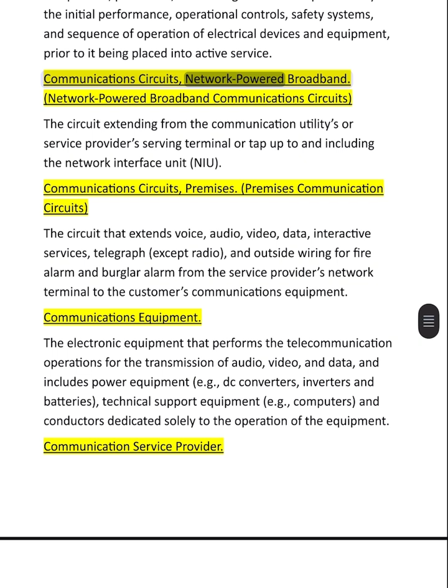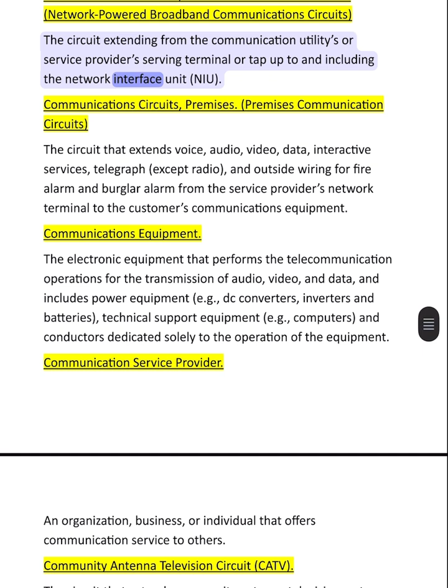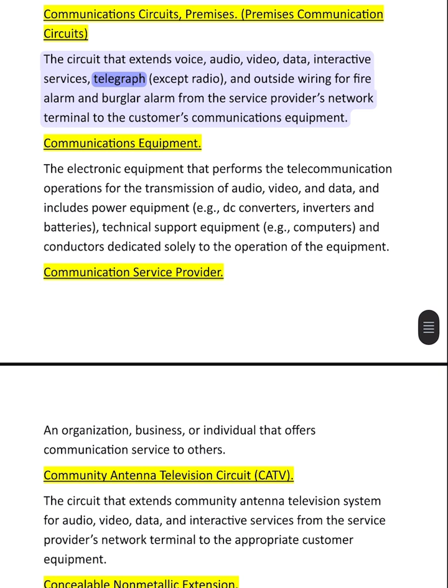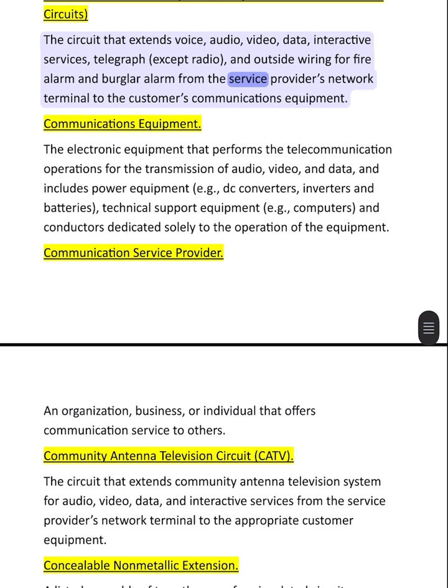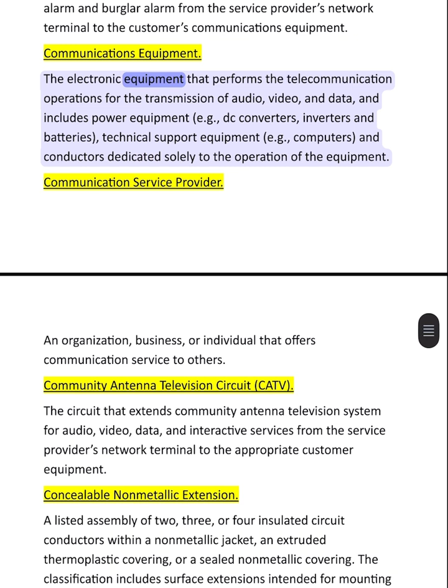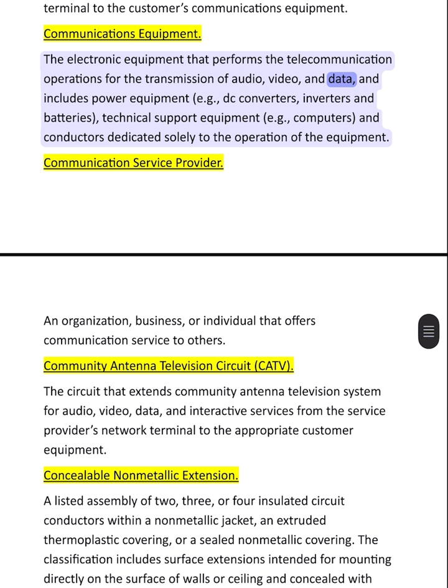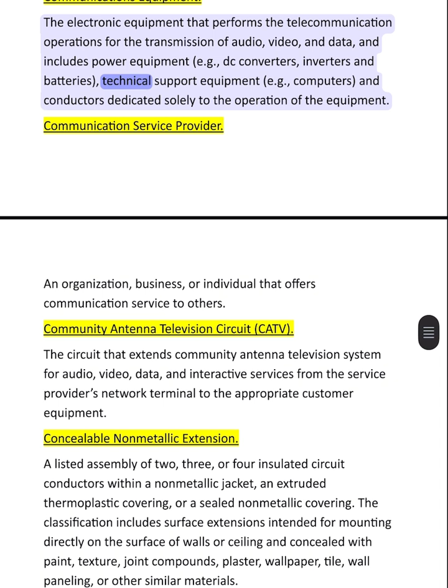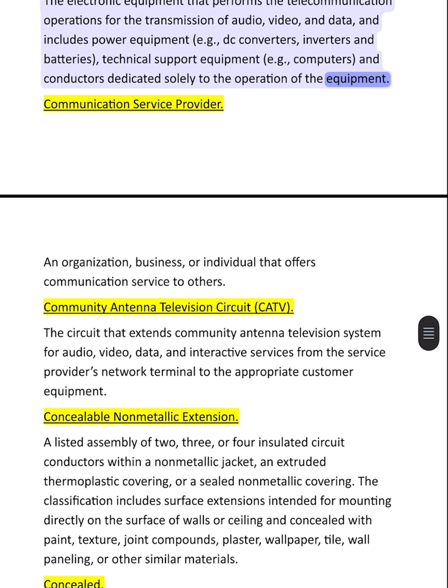Communication circuits, network-powered broadband. Network-powered broadband communication circuits. The circuit extending from the communication utilities or service provider's serving terminal or tap up to and including the network interface unit, NIU. Communication circuits, premises. Premises communication circuits. The circuit that extends voice, audio, video, data, interactive services, telegraph (except radio), and outside wiring for fire alarm and burglar alarm from the service provider's network terminal to the customer's communications equipment. Communications equipment. The electronic equipment that performs the telecommunication operations for the transmission of audio, video, and data, and includes power equipment, for example, DC converters, inverters and batteries, technical support equipment, for example, computers, and conductors dedicated solely to the operation of the equipment.